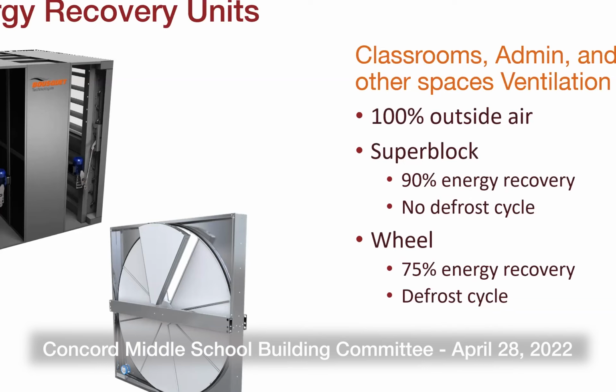So the second one - the energy recovery units and superblock - there are 3 different manufacturers. I'm working with them on another project, getting specific selections from all 3 manufacturers so that we know it can go to a fair bid. The other thing I've set up in the specs previously was allowing for dual wheel versus superblock, making it more of a performance spec of 90% energy recovery, because dual wheel can usually get to that number as well. If a manufacturer wants to bid dual wheel against superblock, we're open to entertaining that, because the major goal is getting more efficient units that save more energy.